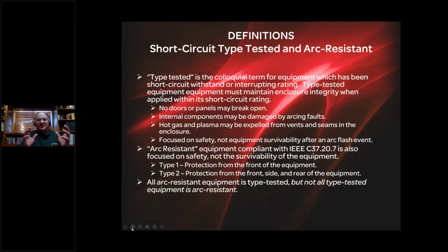So in terms of short circuit type testing, understanding type testing and arc resisting, type testing is focused on maintaining enclosure integrity, and its emphasis is not on protecting the equipment itself. It's not about equipment survival, it's about safety. No doors or panels may break open. Now, equipment that is type tested, whether it's switchgear, a VFD, or a motor control center, that doesn't mean the internal components survive an arc flash event. Again, the arc flash event without an arc quencher at 30,000 degrees Fahrenheit is going to vaporize most materials that you would find inside that equipment.